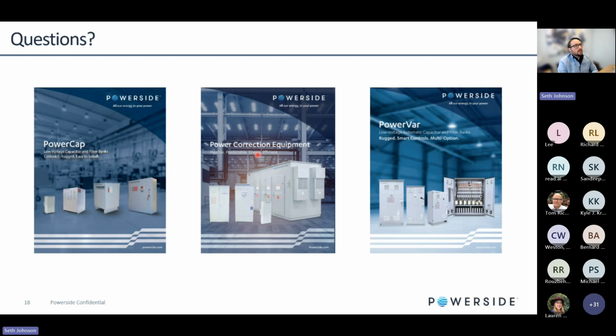Yeah, so you can parallel as many as you want together, but in a single enclosure, we can do 750 amps in one single enclosure. So that's kind of what we have from an active filter perspective. But we've easily paralleled up to 5,000 amps on a single system. We've also done active filtering through a dedicated transformer up to 25 kV bus, 15 kV bus for medium voltage compensation as well.